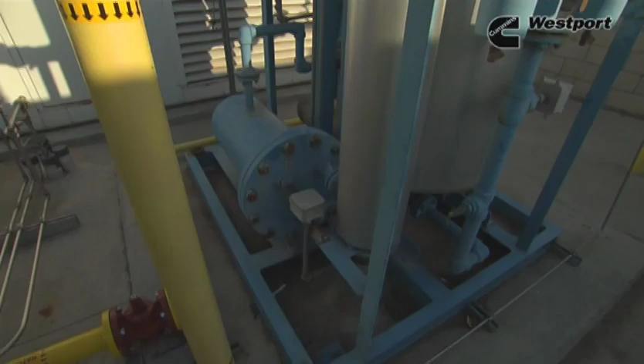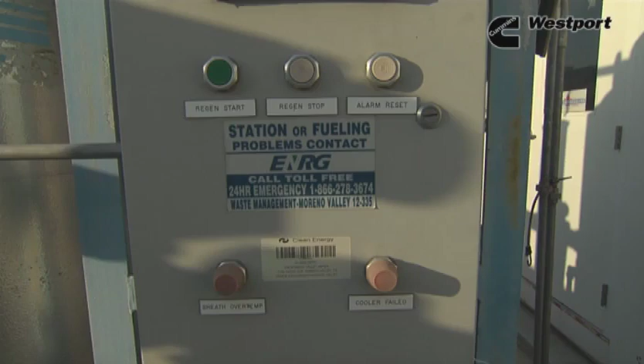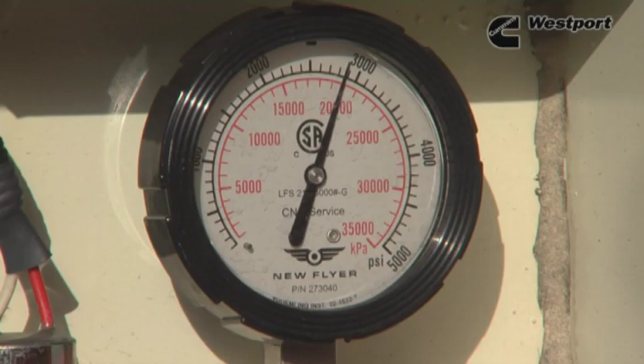And it can take upwards of 15 minutes to fuel one truck. Time fill and fast fill stations are temperature compensated, meaning the final fill pressure depends on the ambient air temperature. When refueling on a day colder than 70 degrees Fahrenheit (21 degrees Celsius), the final settled fill pressure will be less than 3,600 psi. When refueling on a day warmer than that, the final settled fill pressure should be slightly higher than 3,600 psi.